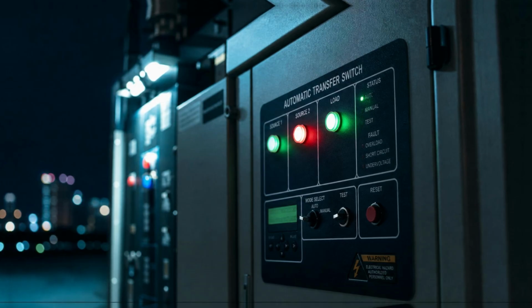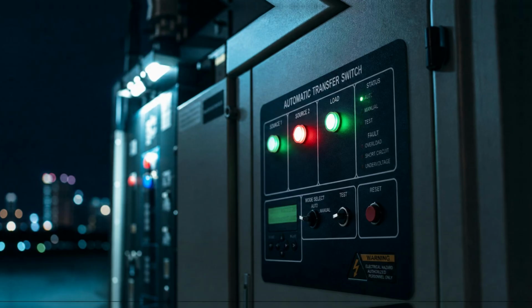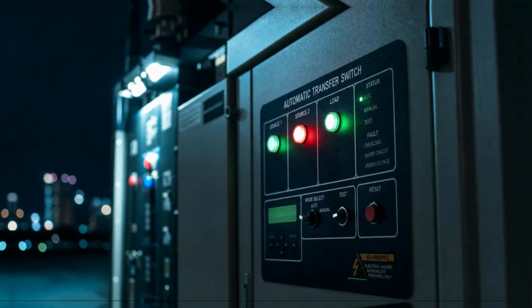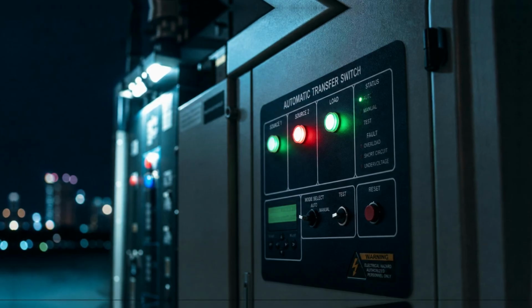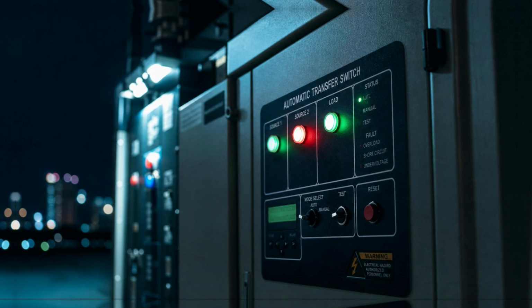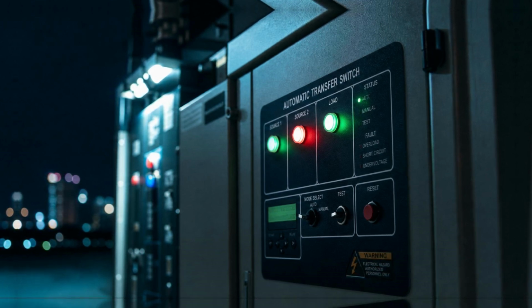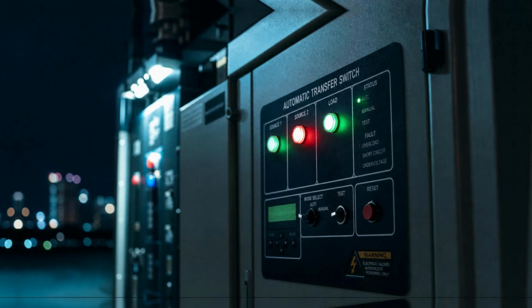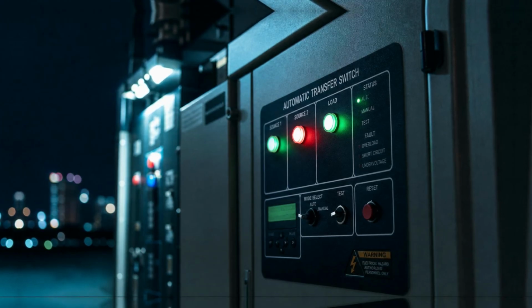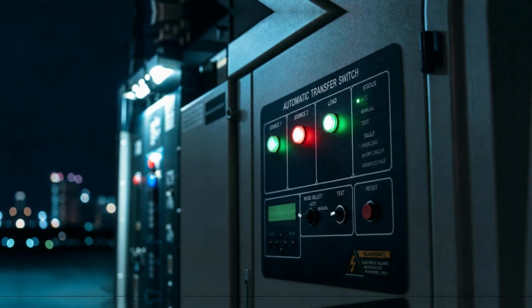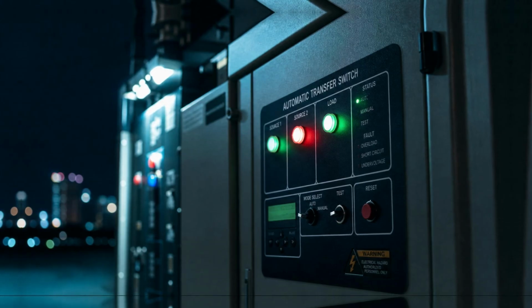The control system watches. It monitors the output. It waits for the voltage and frequency to stabilize within acceptable limits, the same kind of limits that the utility monitoring system watches on the incoming power side. And when those limits are met, when the generator's output has proven itself steady and suitable, the control panel sends its confirmation back to the transfer switch.